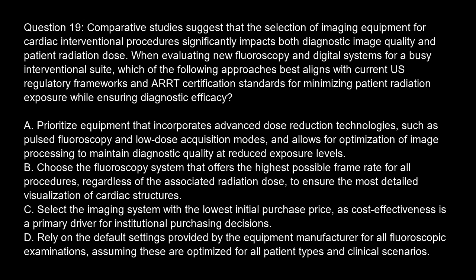The correct answer is A. Prioritize equipment that incorporates advanced dose reduction technologies, such as pulsed fluoroscopy and low-dose acquisition modes, and allows for optimization of image processing to maintain diagnostic quality at reduced exposure levels.